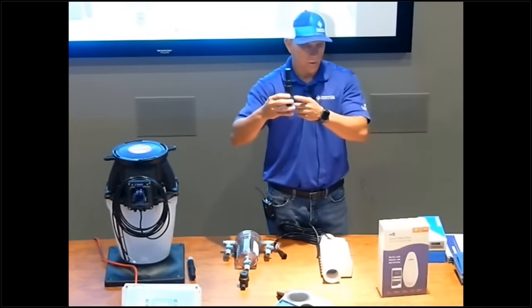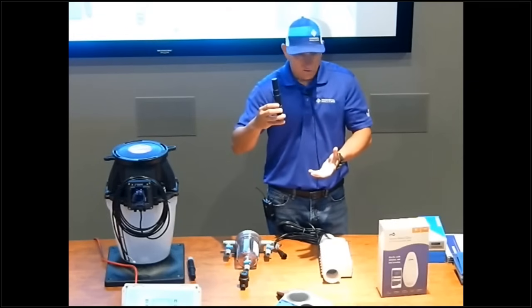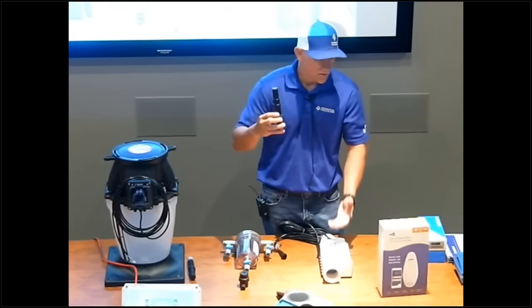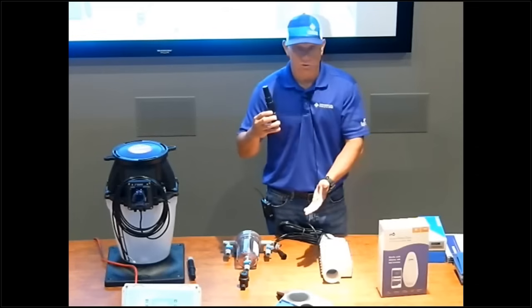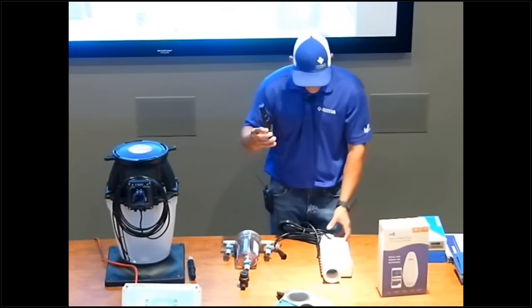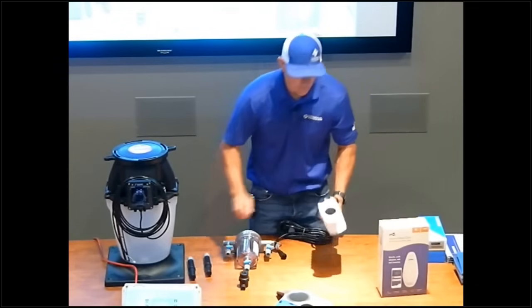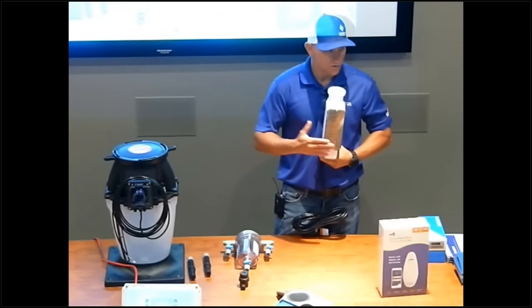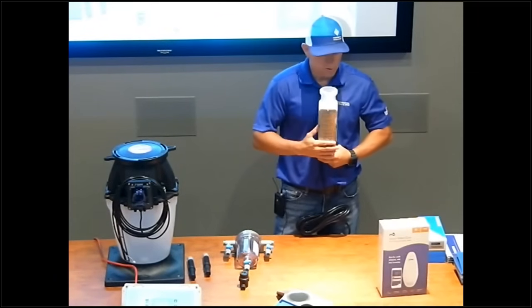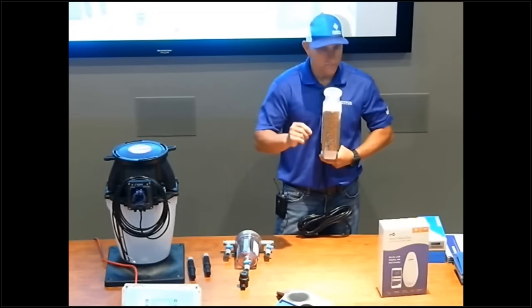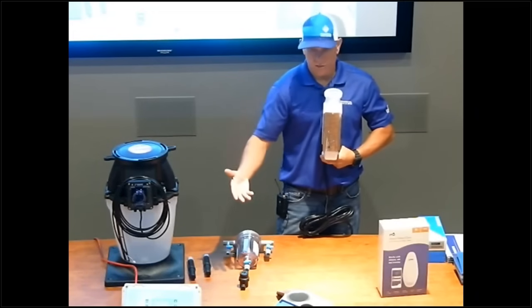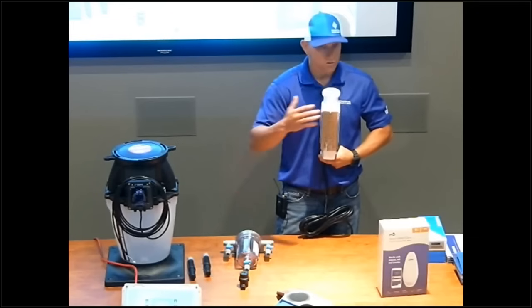Basically, this senses the free chlorine in the water and then tells the salt chlorine cell to turn on or off. The only difference between this and what you already have is that when the cell gets turned on, it's turned on at 100% for a brief period of time, and then it turns off. Then it readjusts, tests again, and turns the cell on and off.